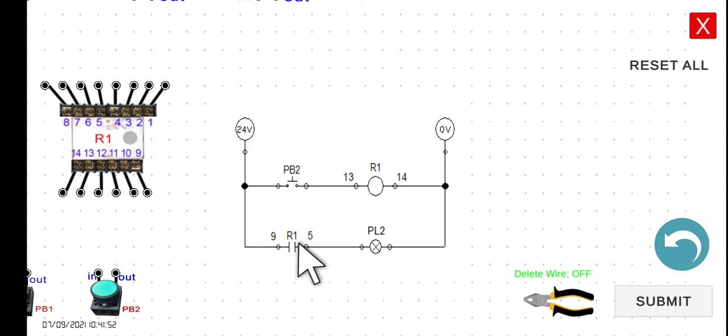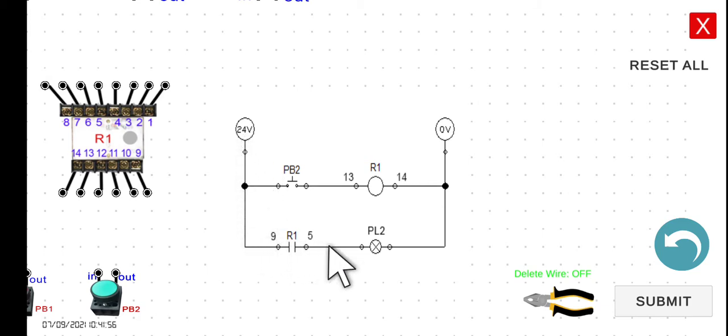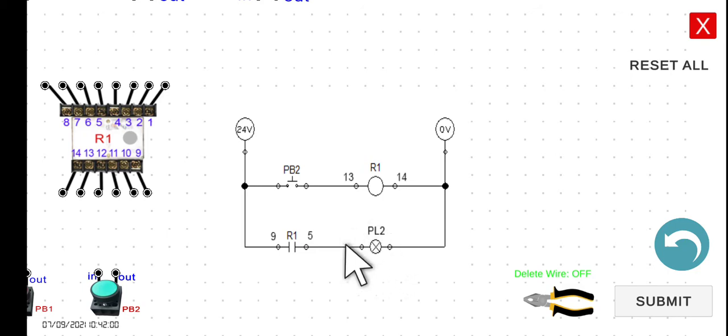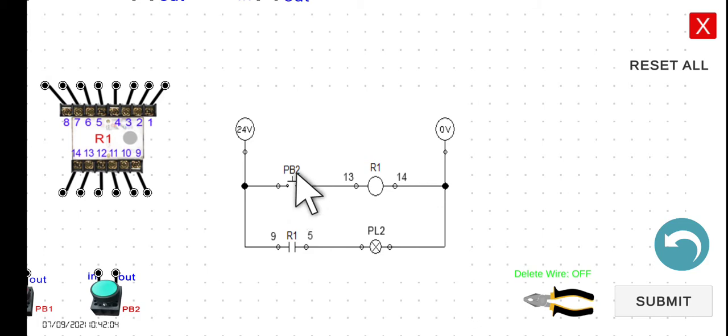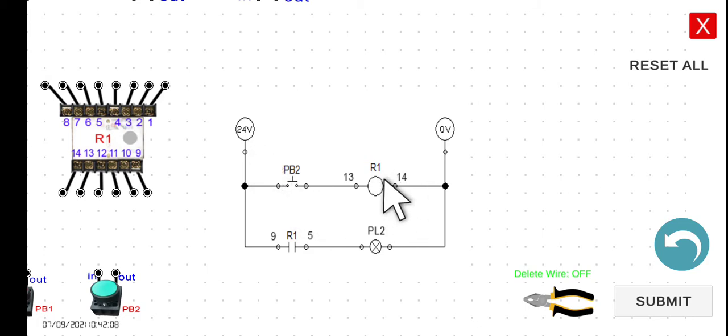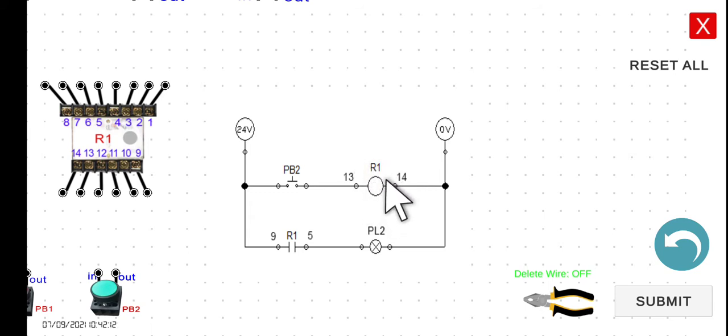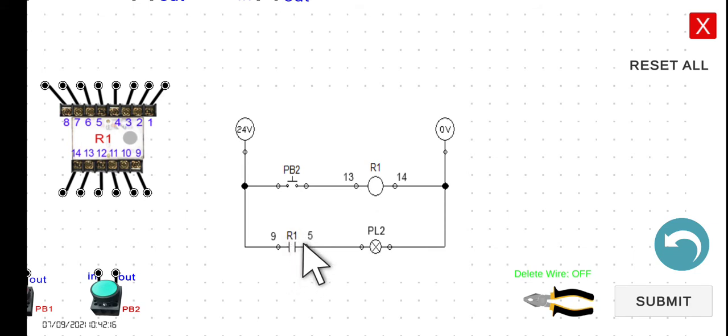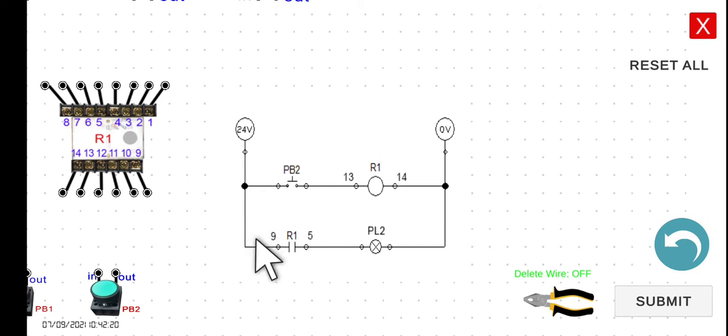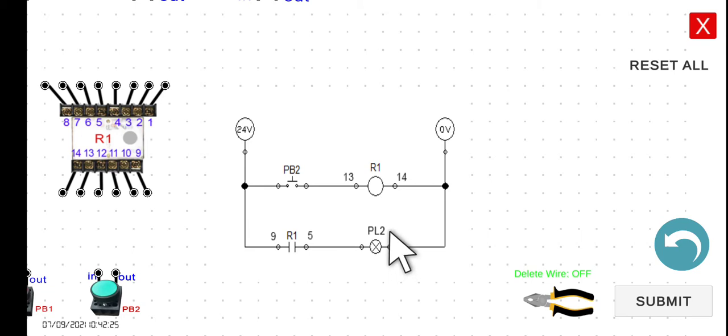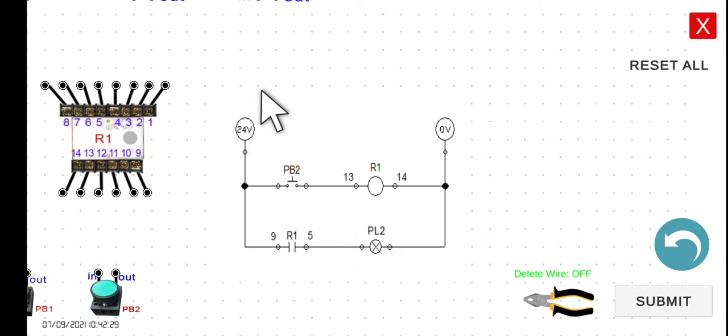If this will close, the current now will be able to flow from the 24 volts through this PL2. Hence, this PL2 will turn on. However, if you release your hand in this PB2, the current now will not be able to flow through this R1 here. Hence, it will become de-energized. If this one is de-energized, this R1 will return to its normal state, which is normally open. Hence, the current now will not be able to flow through this PL2, and this will turn off. In summary, if you start this 24 volts power supply, this PL2 is turned off. However, if you press this one and hold, this will turn on. And then if you release your finger in this push button, it will turn off.